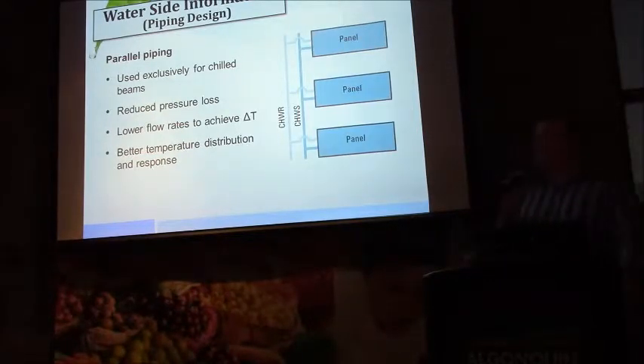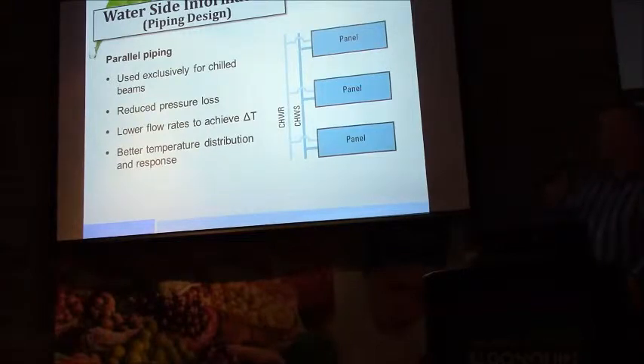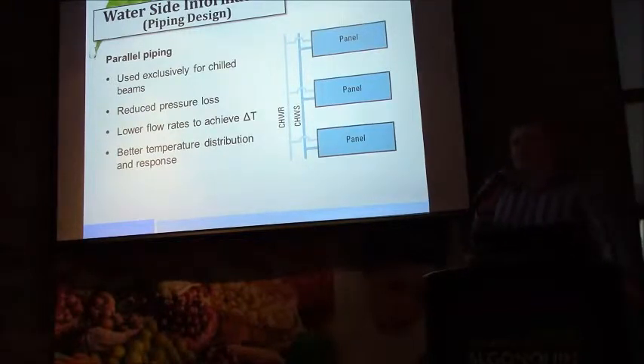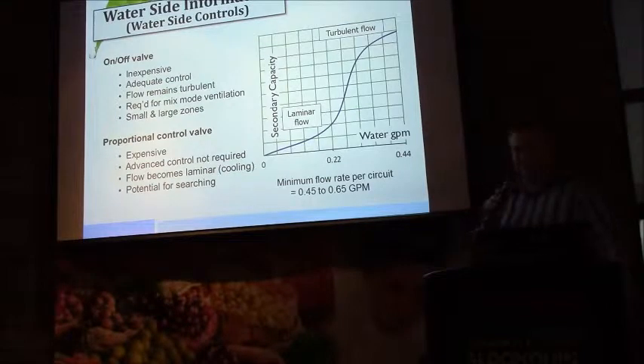Every beam needs to see the same chilled water temperature. Cascading the chilled water complicates the selection process exponentially. And so effectively every beam needs to see the same supply water temperature, which as a general rule for the design could be 60, 55.